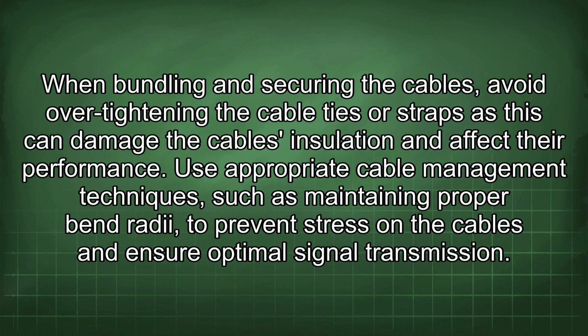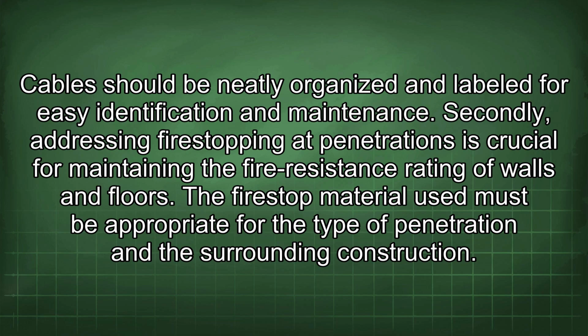When bundling and securing the cables, avoid over-tightening the cable ties or straps, as this can damage the cable's insulation and affect their performance. Use appropriate cable management techniques, such as maintaining proper bend radii to prevent stress on the cables and ensure optimal signal transmission. Cables should be neatly organized and labeled for easy identification and maintenance.